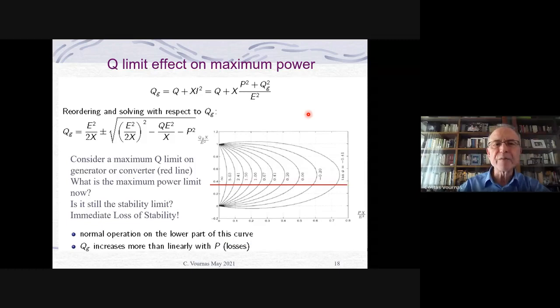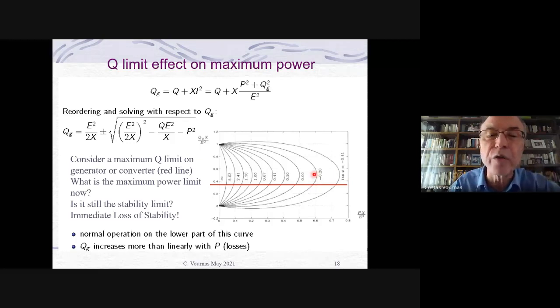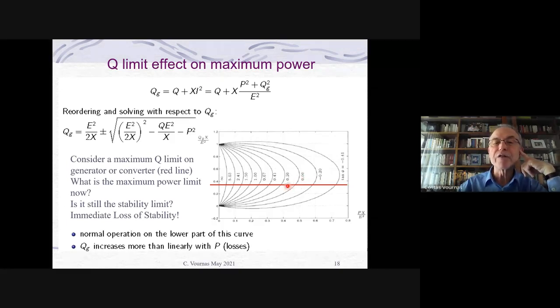So what happens if this power is limited? So my source does not have enough power to go to the maximum power. For instance, in the case of unity power factor, I don't have 0.5 of the short circuit power, but I have something less than 0.4. So I stop in this line. What happens is that as my load increases, I can go up to this point, but I cannot go beyond, because to go beyond, I need more reactive power.